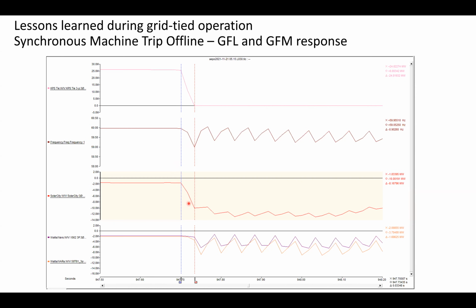On the third plot down in red, you'll see we have a grid forming inverter. As soon as frequency starts to decline, almost instantaneously, you'll see a real power response. This is an inertial response type from this grid forming manufacturer with zero delay, as compared to the purple and the yellow real power trends at the very bottom. These are both grid following inverters.